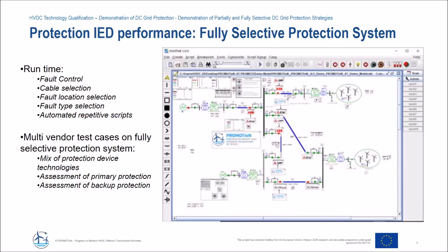From the runtime, this is where we could control the fault type and which cable the fault was on, and then we could set up the automated testing using a script to run through all these tests to get a good understanding of the performance of the IEDs and of course the overall test system. By using this mix of different technology devices and IEDs, it really let us push the multi-vendor aspect while also assessing the primary and backup protection in terms of system level KPIs. Now, there'll be more details of that given at the demonstration event on Wednesday 9th, or if that's passed, then there'll be some information available on the website based on that.